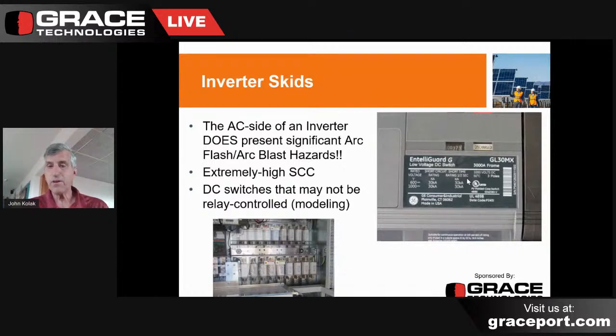And then you also encounter something on this that's maybe unique, and that is the DC switches may not be relay controlled. In other words, they may be actually used just for a switch. So, for example, I've got a picture of this EntelliGuard. You see it's a low voltage DC switch. Well, in this case, I should have had the slide pictured, on the upper left side of that same nameplate, there's a place where you could put a trip system and a trip relay in there. But in this case, this is absolutely used just as a switch.